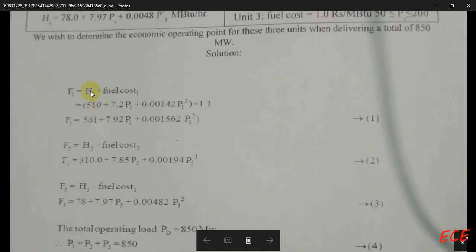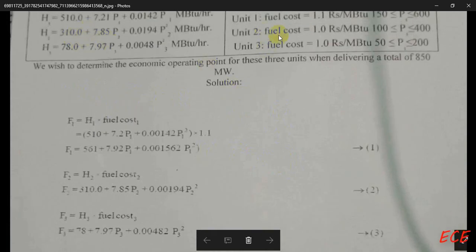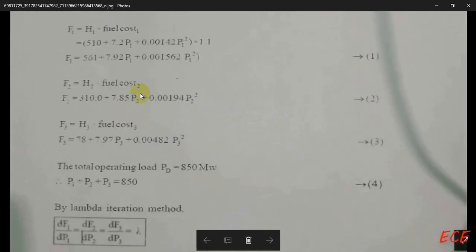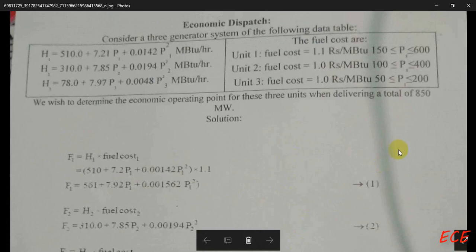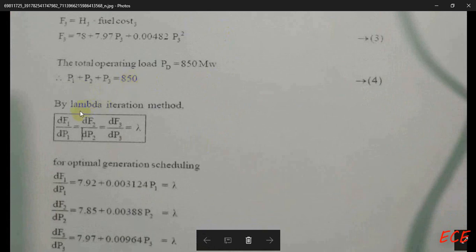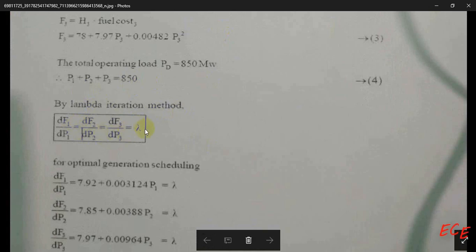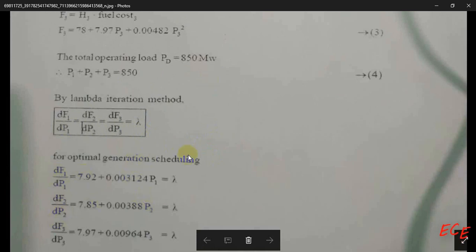First, we need to calculate F1 by multiplying H1 with the fuel cost, which gives us a cost equation. Similarly, we get F2 and F3. Then we write the equation for the total power: P1 plus P2 plus P3 must equal 850 megawatts. After this, we differentiate the cost functions and set each derivative equal to lambda.